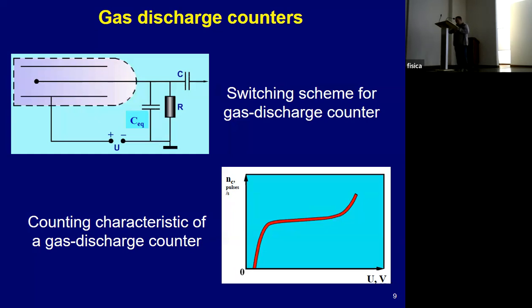To some extent, the energy dependence of the counter sensitivity can be reduced by using additional filters. However, it is more reliable to calibrate devices with counters by radiation of a spectral composition which is close to that measured in practice.